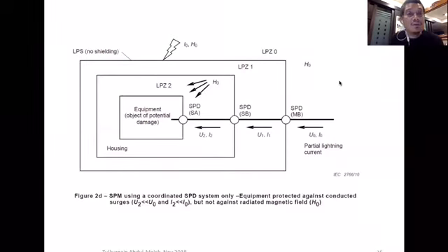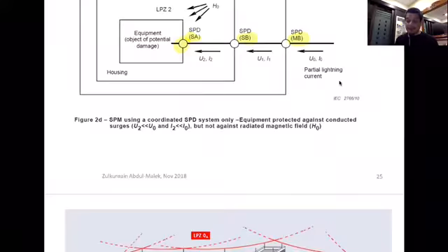In this case, there is no shielding for both zones, but the SPD is defined as reducing from zone 0 to zone 2. And the equipment itself also has no shielding, but you have an extra surge arrestor before the equipment itself. So it's good. You have one at the main board, one at the switchboard, and one at the equipment itself. Before the equipment, it's like your PC.